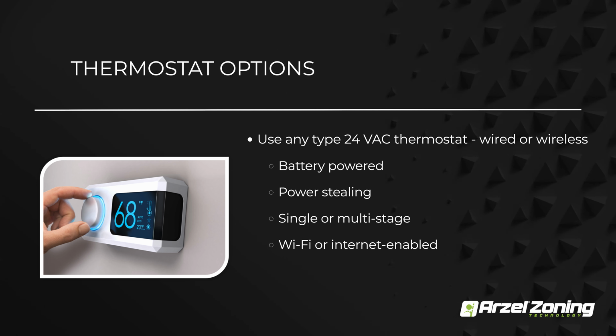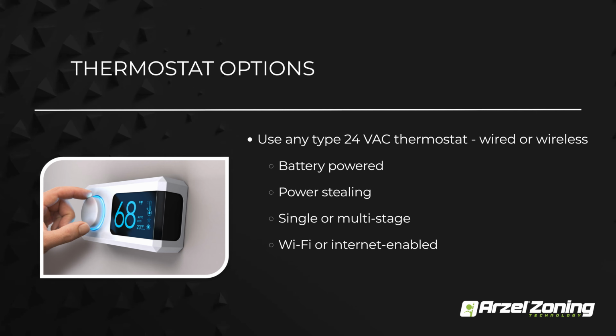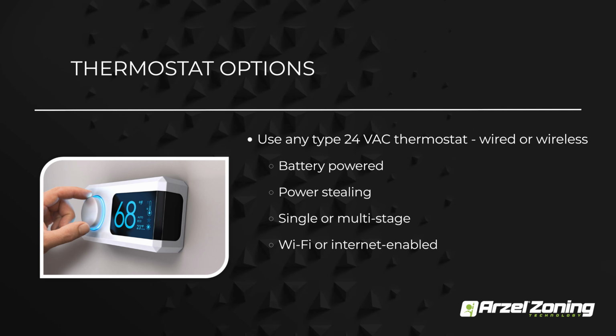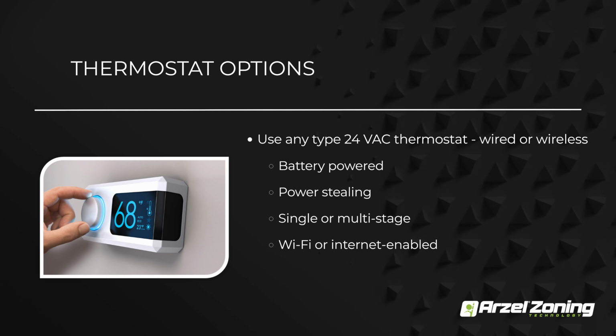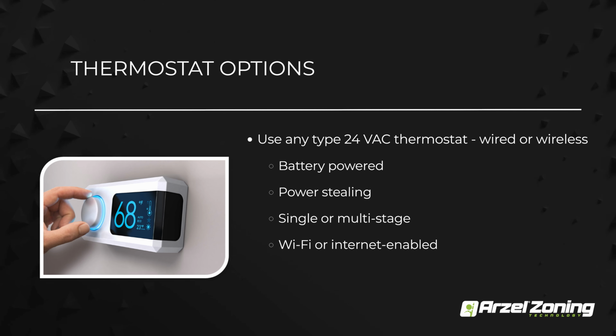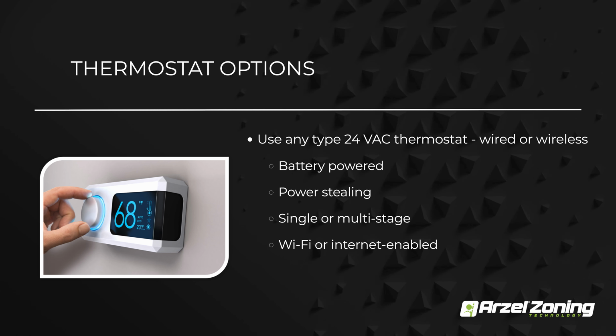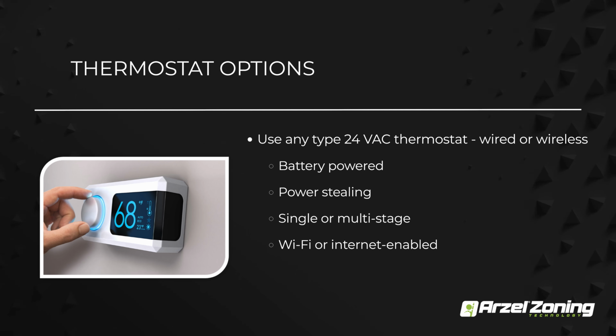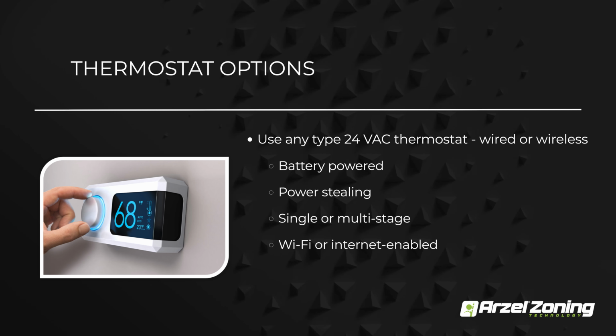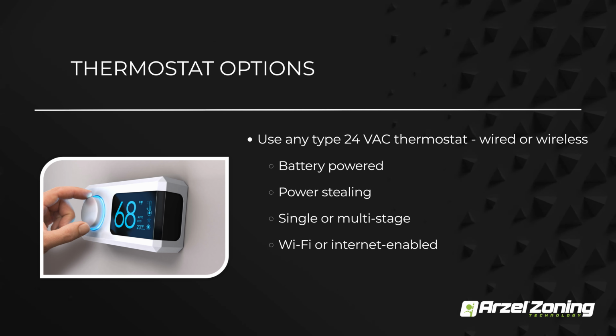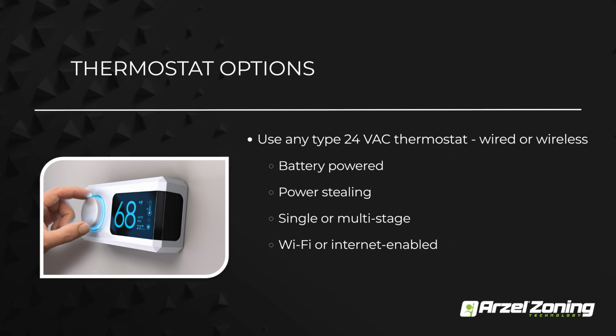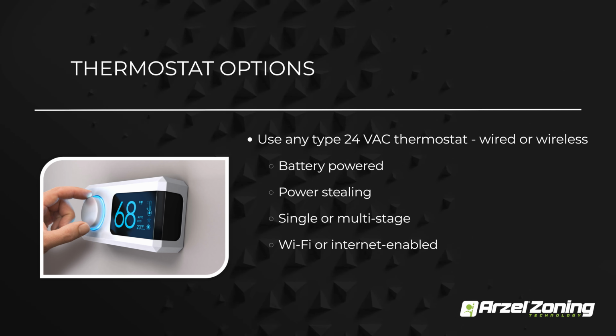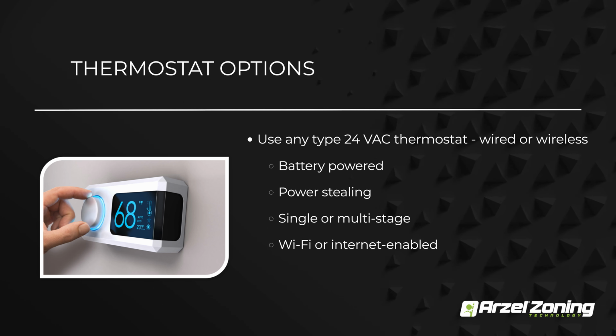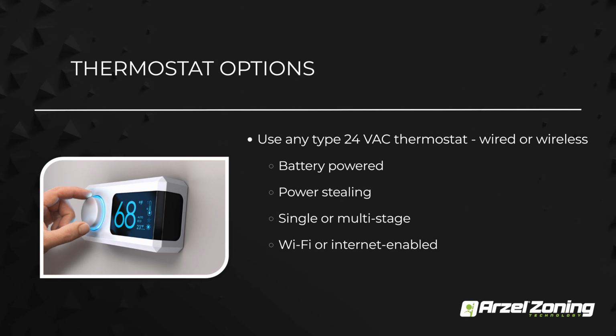The only thing that we recommend if you guys are doing like a Nest or an Ecobee, if you don't have a common wire, make sure you run a common wire. Don't use a wire saving kit. They will cause some issues with zoning panels in general. So if you guys are doing that, you're going to want to do either a wireless stat with a module if you can't run the wires, or any kind of wireless stat would work as well. With the Nest though, the only option they give you is that wire saver, so don't use that. Make sure you have that common wire.